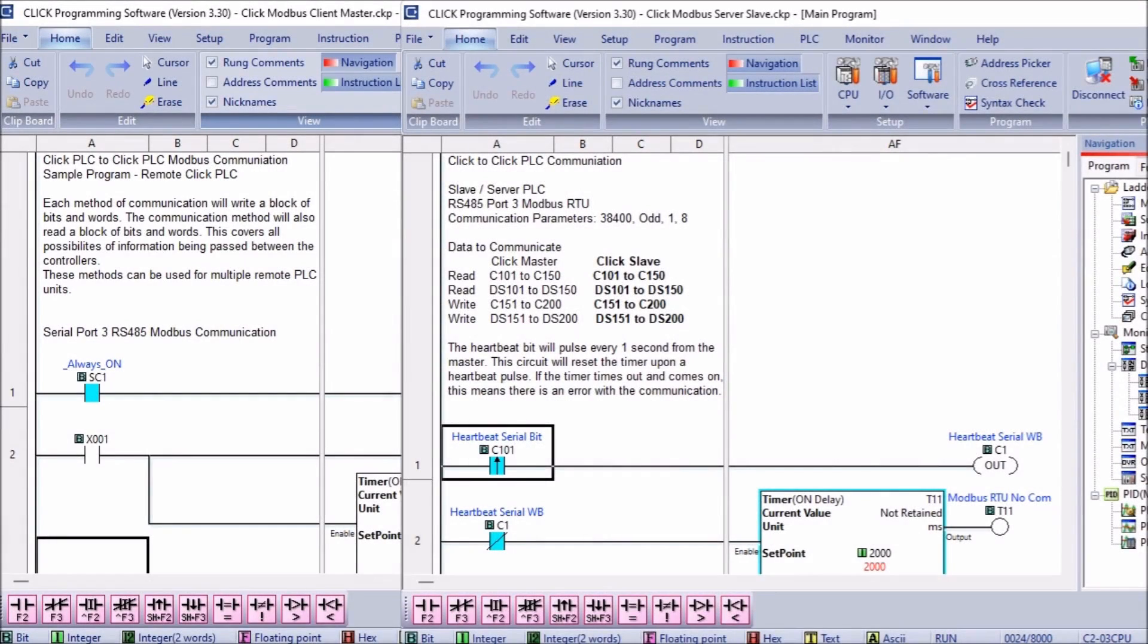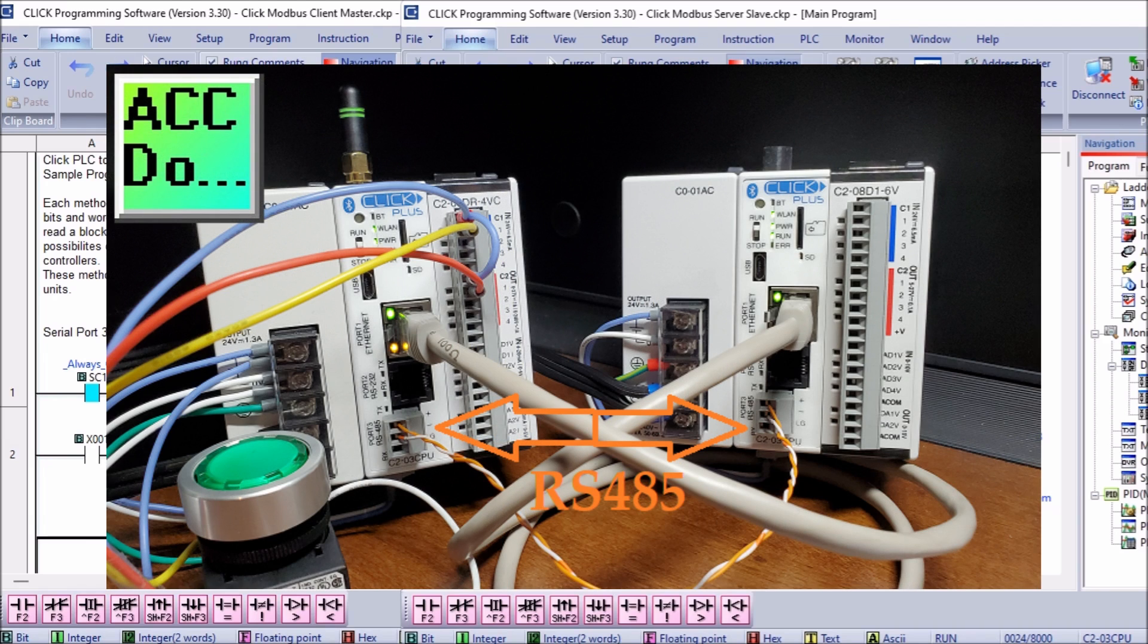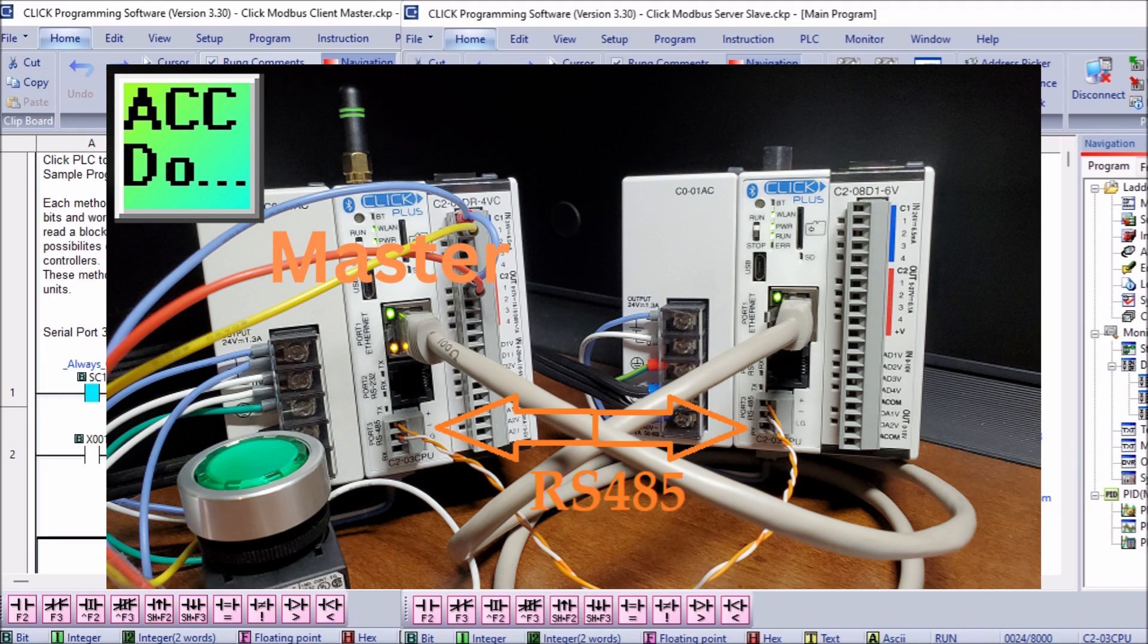The RS-485 Modbus RTU connection is a two-wire twisted pair. The communication parameters must be the same for the master and all of the slave units. In Modbus serial communication like Modbus RTU, the controller sending the commands is called the master.